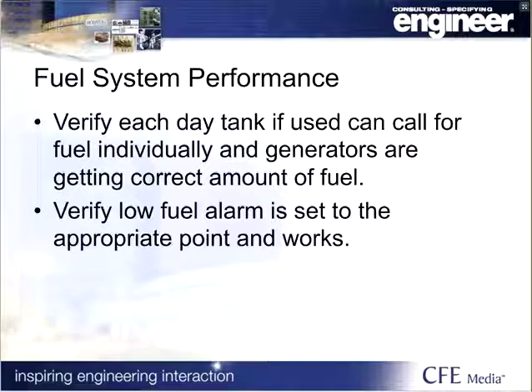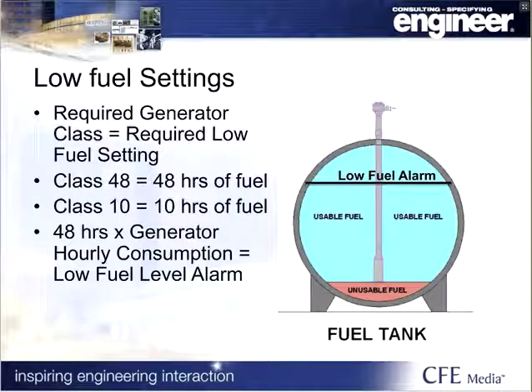We also want to verify that if there's a main tank, the low fuel alarm will set off an alarm in the building and in the generator switchgear to let everyone know that they need to reorder fuel. So typical low fuel settings would be, if it's a class 48, you're going to have 48 hours of fuel. And at 48 hours of fuel left, you have to alarm the 24-hour location to let them know to reorder fuel.